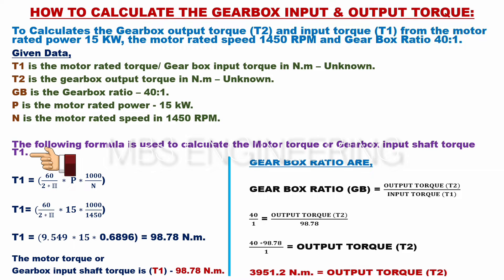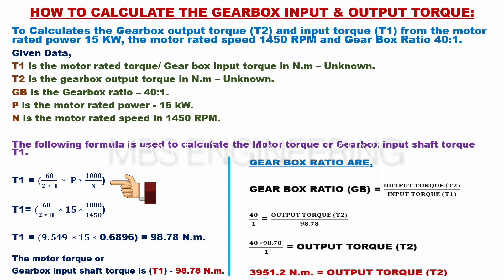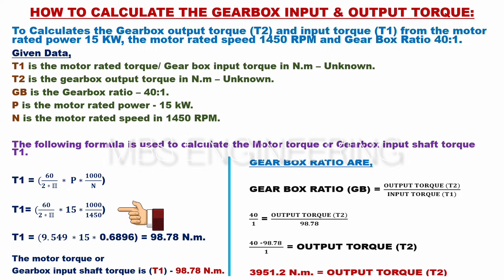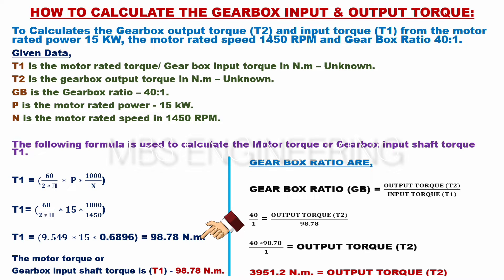The following formula is used to calculate the motor torque or gearbox input shaft torque T1: T1 = (60 × P × 1000) ÷ (2 × π × N). Applying the given data: T1 = (60 × 15 × 1000) ÷ (2 × π × 1450), which simplifies to 9.549 × 15 × 0.6896. The gearbox input torque T1 is 98.78 newton meters.